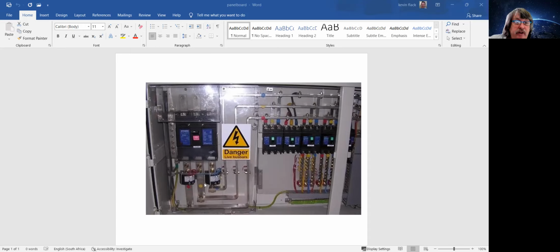We've got CTs connected on the load side. So for a product in the 600 amp class, we can possibly anticipate something between 20 and 30 kA as the short circuit. The lead through into these busbar areas will be in the region of 12 to 15 kA. And as such, these bus bars would have to carry the current that it would have here. It has to deal with the voltage, so they've got to have independence from each other and not be allowed to be connected closely.